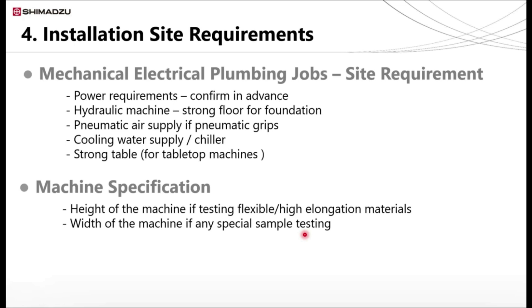For tabletop machines, arrange strong tables. We have one experience at a customer site where, upon keeping a 500 kilogram machine on the tabletop, the table bent, and we had a very tough time taking the machine back from the table and reinstalling it on another table. Height of the machine is also an important aspect every UTM customer should know in advance. We have experience with one customer where, when we installed, the machine was touching the roof of the laboratory. Width is also important. Sometimes customer samples are wide, for example corrugated carton, some non-uniform samples, etc. In such cases, make sure the machine width is enough to accommodate the sample.